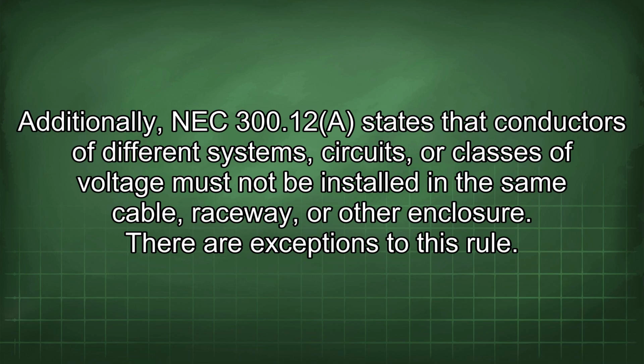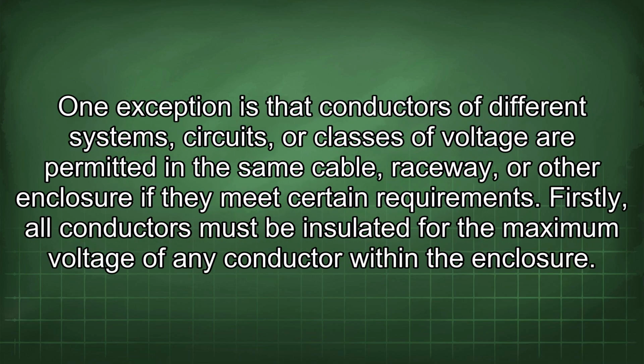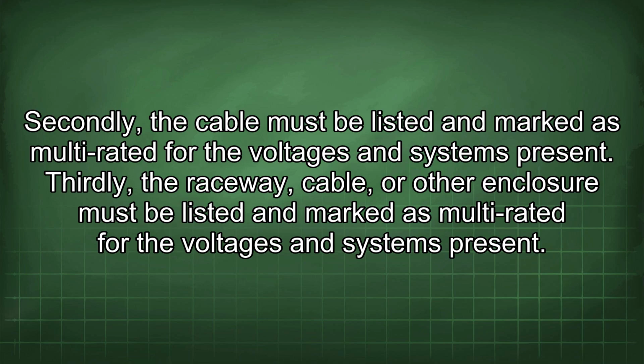There are exceptions to this rule. One exception is that conductors of different systems, circuits, or classes of voltage are permitted in the same cable, raceway, or other enclosure if they meet certain requirements. Firstly, all conductors must be insulated for the maximum voltage of any conductor within the enclosure. Secondly, the cable must be listed and marked as multi-rated for the voltages and systems present. Thirdly, the raceway, cable, or other enclosure must be listed and marked as multi-rated for the voltages and systems present.